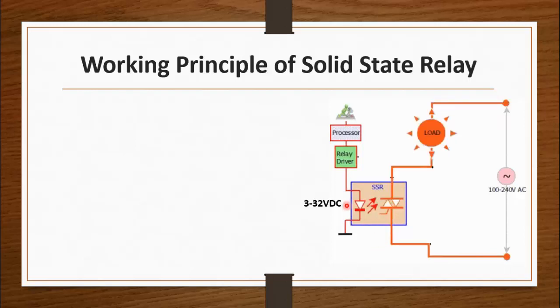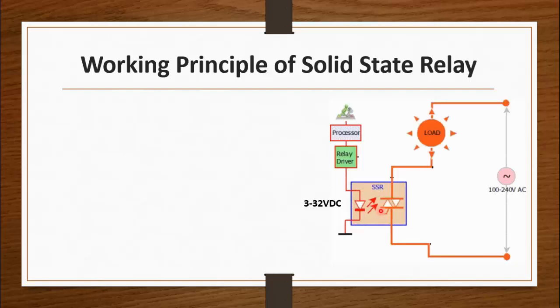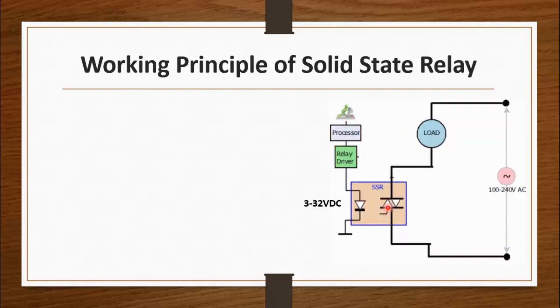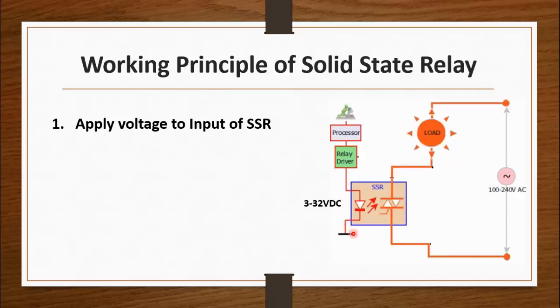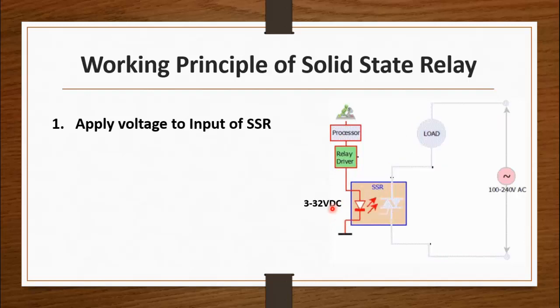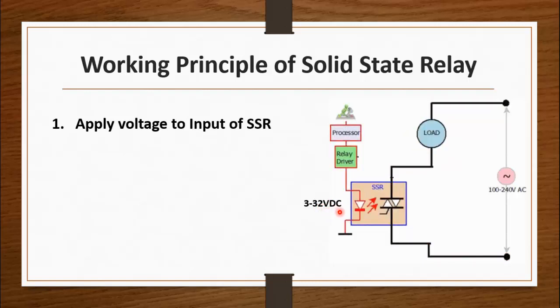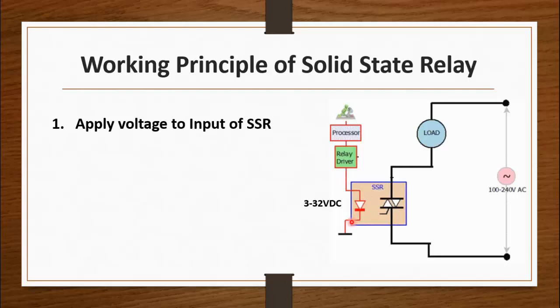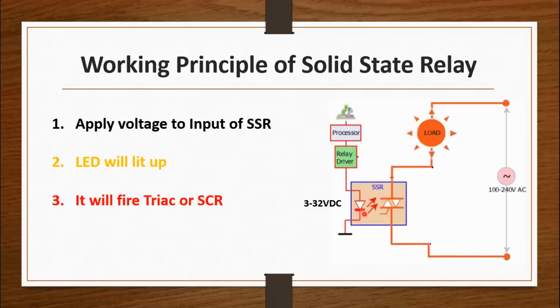This is a block diagram of a solid state relay in which you can see an LED and a solid state component, which may be a triac or an SCR. First, you apply the input voltage to the input side of the SSR, which means you are energizing an LED. The voltage range of the SSR is between 3 to 32 volt DC, and it also comes in an AC model. When you apply voltage, the LED lights up and fires the triac, which in turn energizes the load.